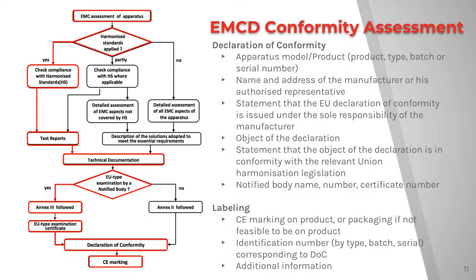The CE marking is a key indicator but not proof of a product's compliance with the EU. There are no specific color requirements for the letters and background of the CE mark. In other words, it is not required to print the letters CE in black against a white background. However, the color schemes for the foreground and background should be sufficiently complementary so that the CE logo is clearly visible, and the vertical dimension should be no less than 5 mm. Products must also be accompanied by additional info, such as contact information and use or installation disclaimers.